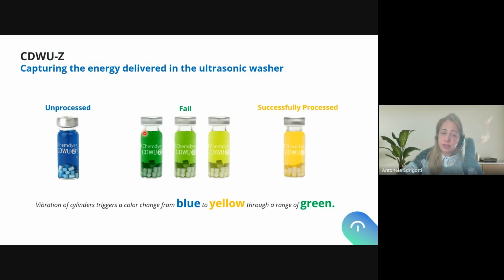The vibration and the energy delivered to the indicator at the location where it is positioned will, with the right energy, trigger a chemical reaction, thanks to the vibration of the ceramic cylinders. This chemical reaction will move from blue to yellow through the different shades of green. So if we don't arrive at the final yellow color, it means that the cavitation energy delivered to that indicator was not enough to guarantee the cleanliness of our instruments. So that's the concept.